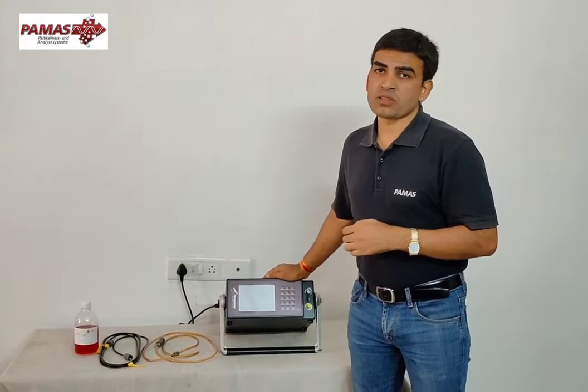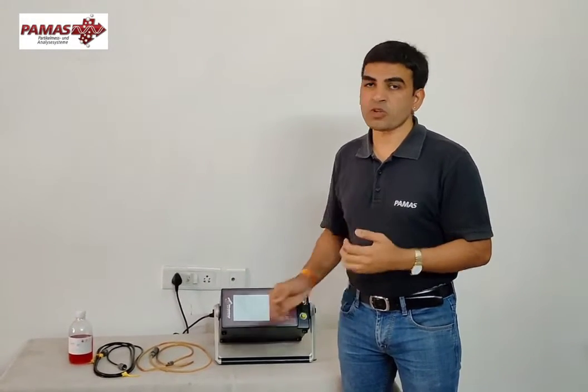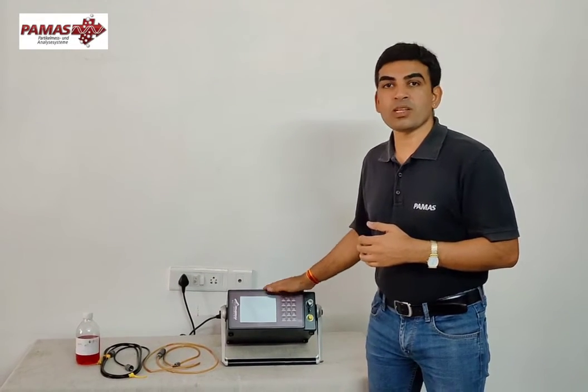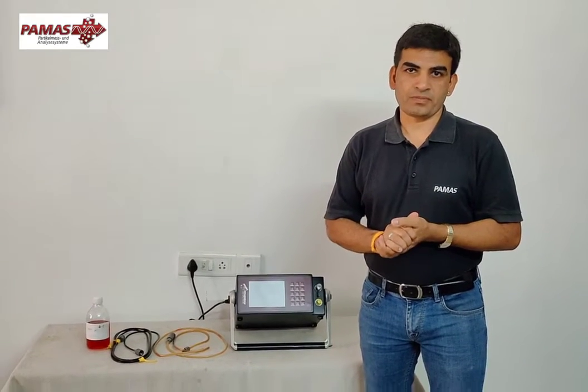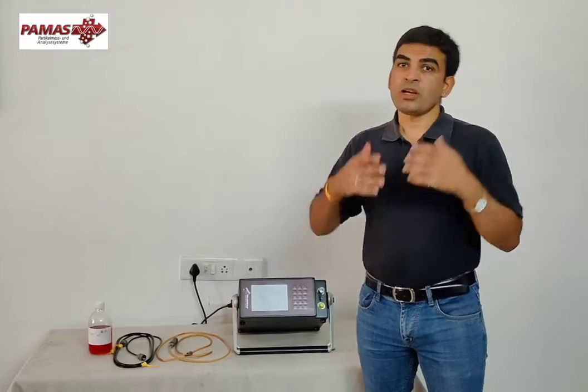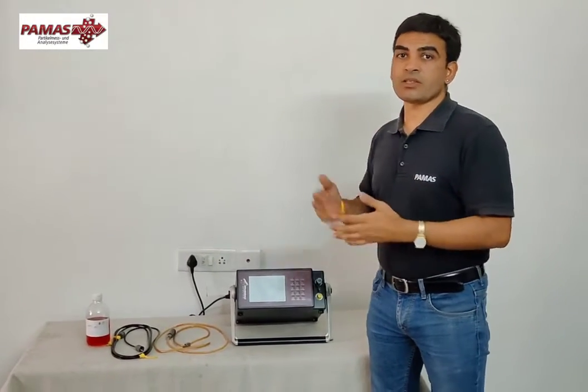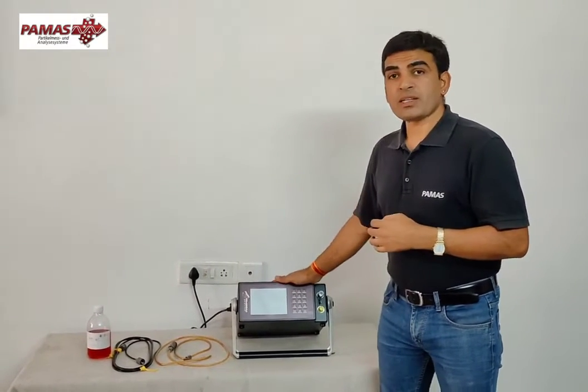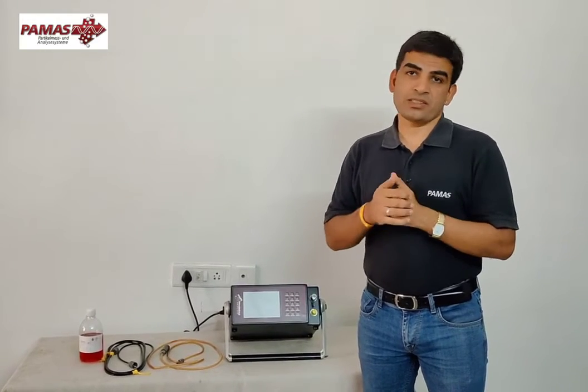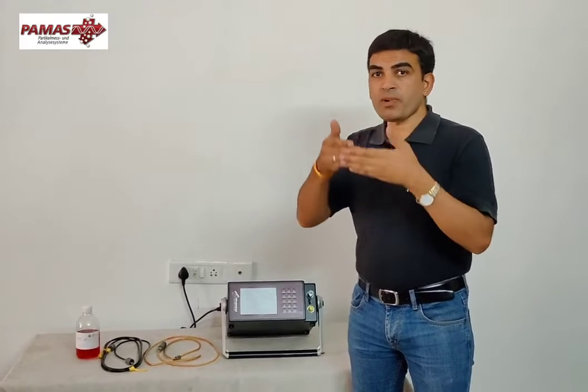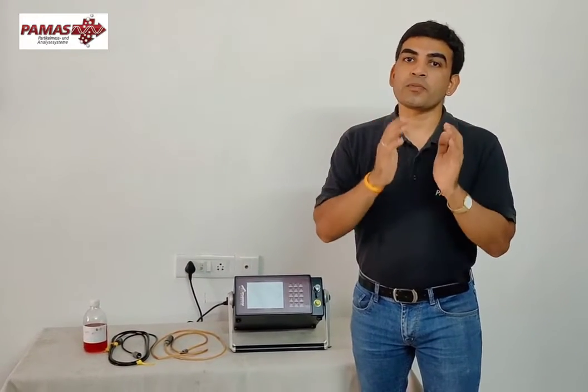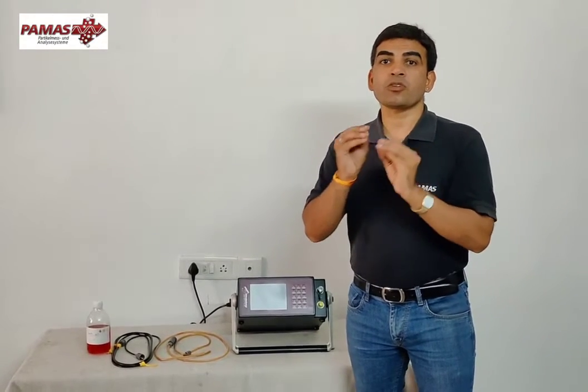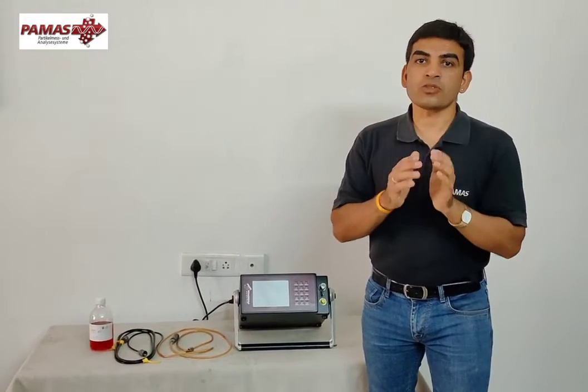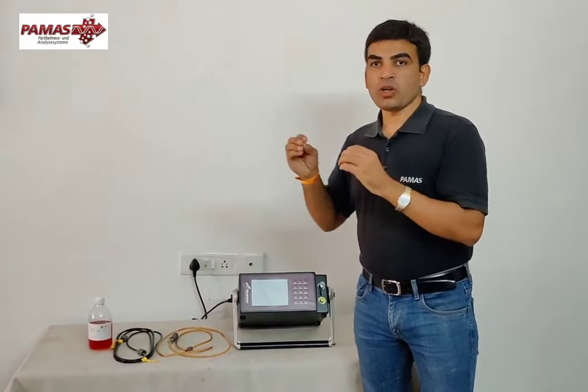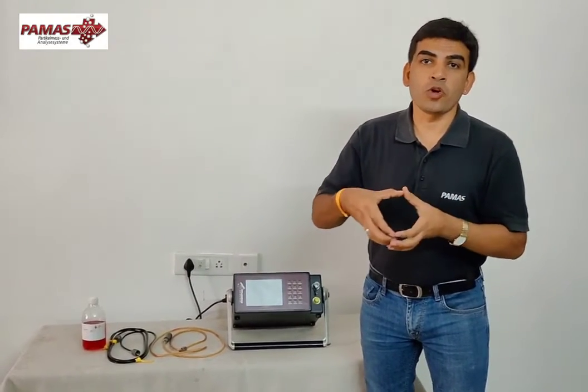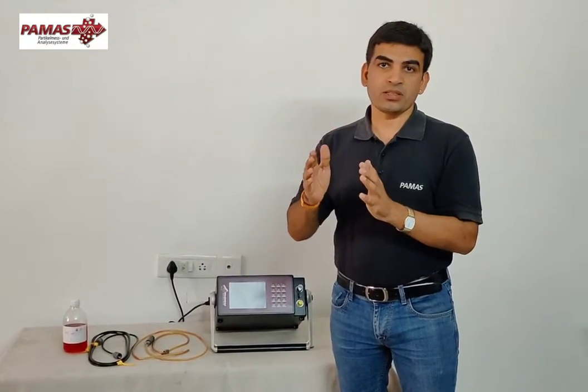This portable liquid particle counter has many extraordinary features. First of all, the sensor we are using in this instrument is a laser based sensor. We at Pamas manufacture very highly sensitive sensors to check particle contamination. This instrument has a volumetric sensor. What is a volumetric sensor? It means whatever sample we feed to the system, it will check 100% of that volume for contamination. There is no chance of particles escaping the counting. That's why we call it a volumetric sensor. 100% of the volume which we feed to the system will be counted and checked.